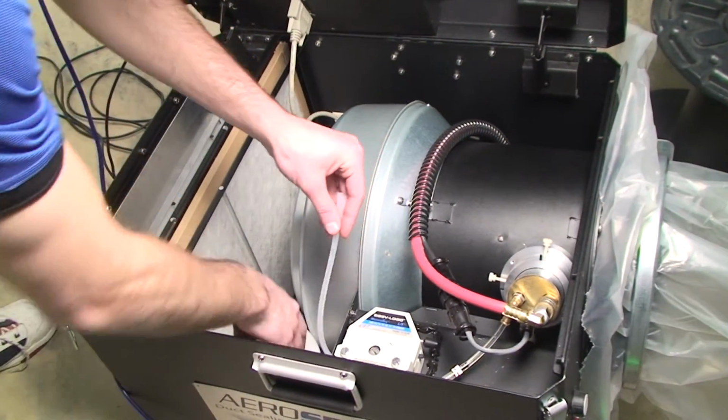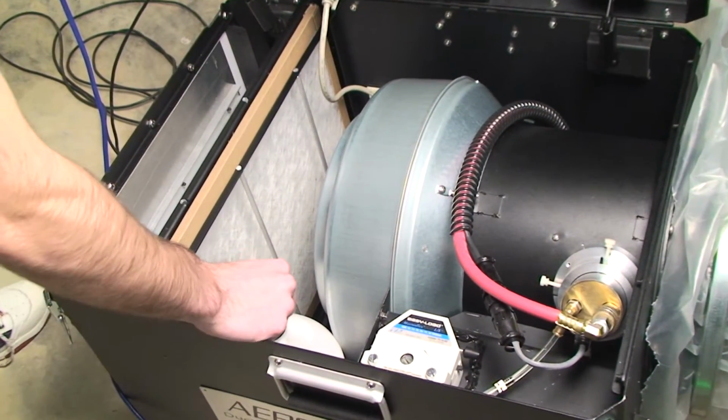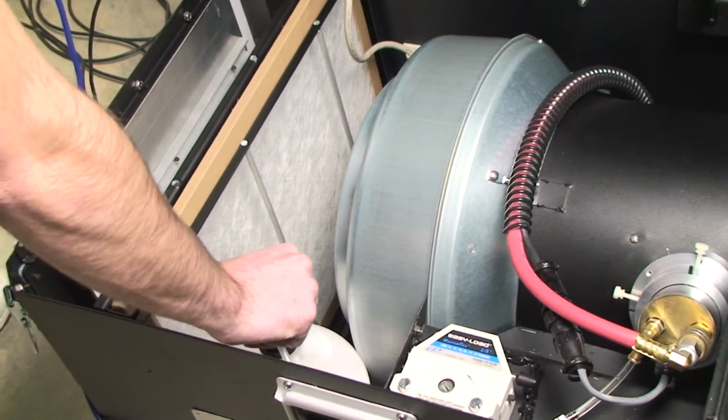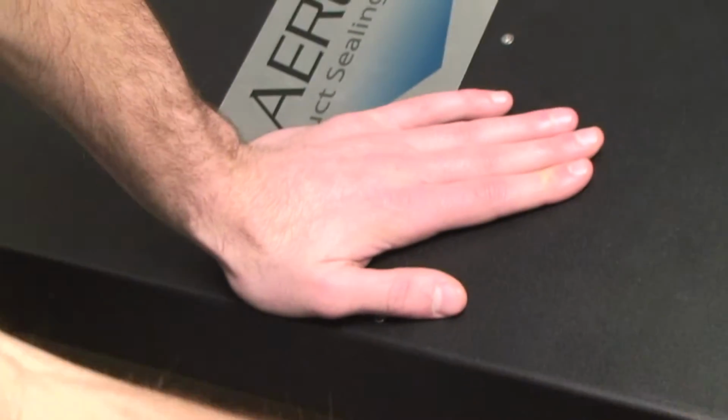One of the only systems I thought would work for me was an aerosol-based injection system. My duct layout is very complicated and not accessible, so an aerosol injection system was a very good fit for me. And when we did it, we reduced the leakage from over 600 CFM down to about 80. So that's like an 80% reduction in leakage. Can you imagine how much waste I had in this particular house? But I knew that going in.